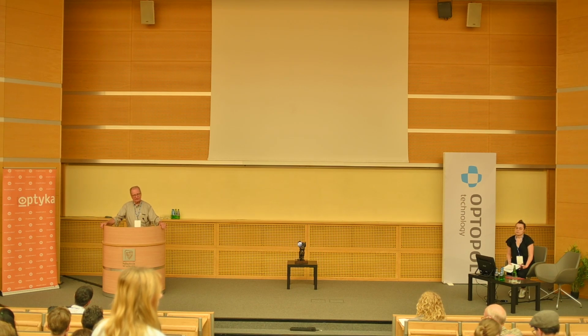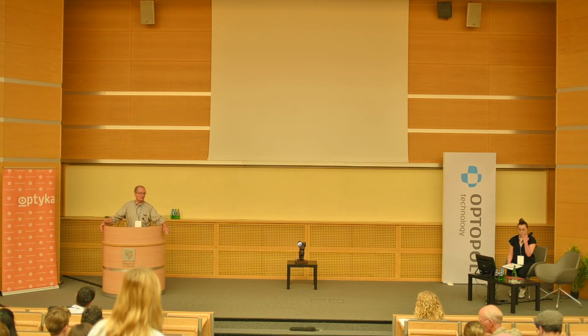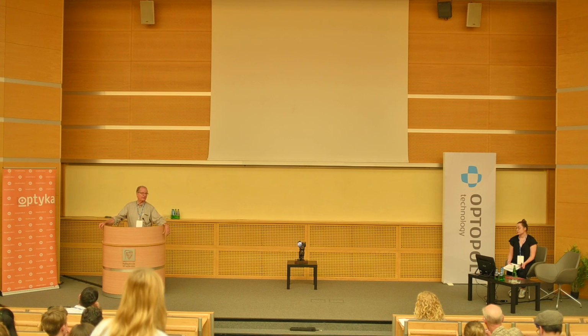And that occurs in very, very highly aberrated eyes. For the most part, the fit has allowed us to design a correction that would return visual image quality to normal levels or above normal levels, quite above normal levels, in fact. But the problem is those lenses are hard to make. So I would put almost all the problem not on the wavefront error measurement if you're using a high density Shack-Hartmann aberrometer. I'd put it on the manufacture of the lens. And that's one thing we just don't have good feedback on. I hope that helps you.